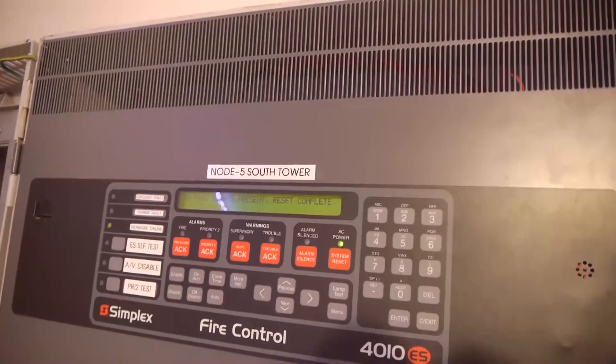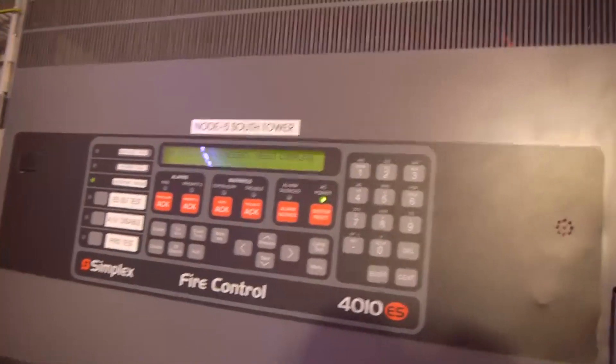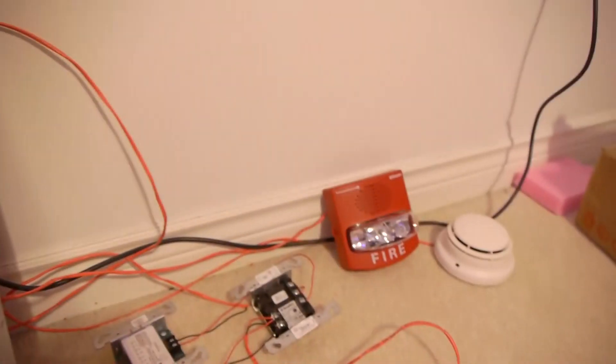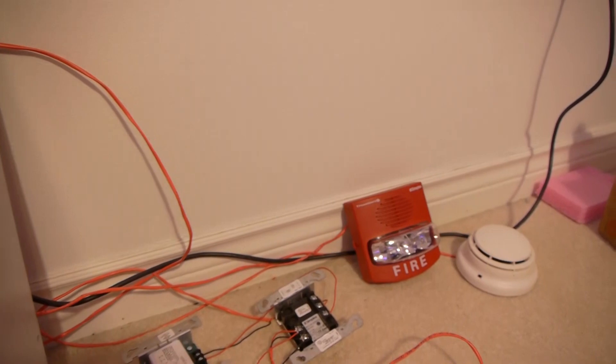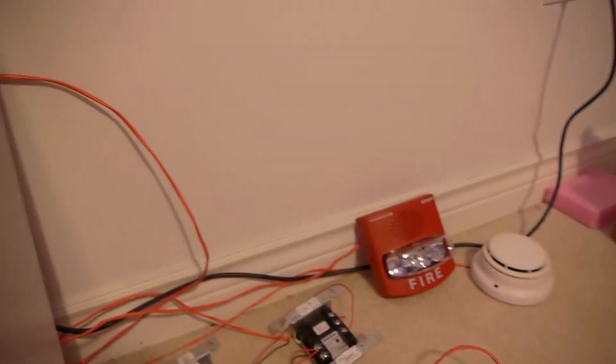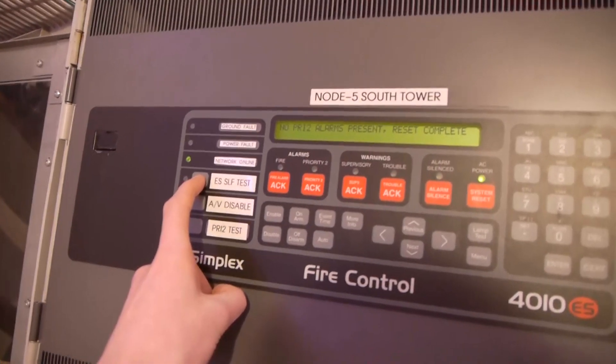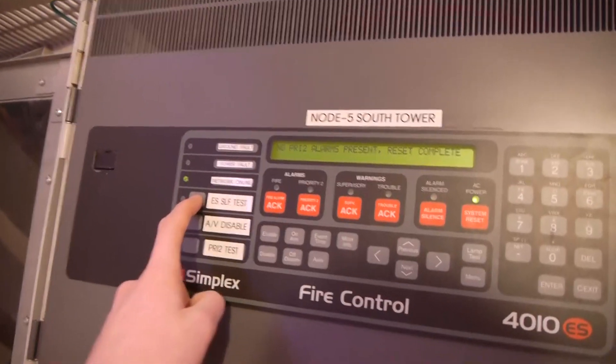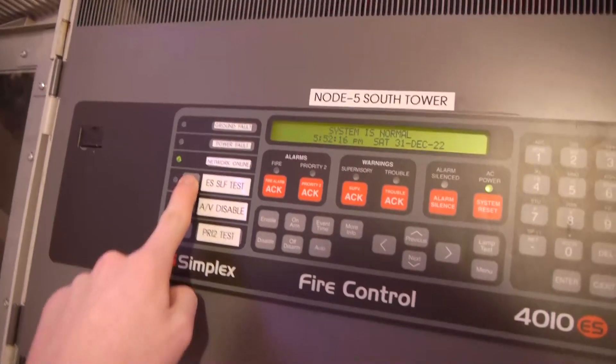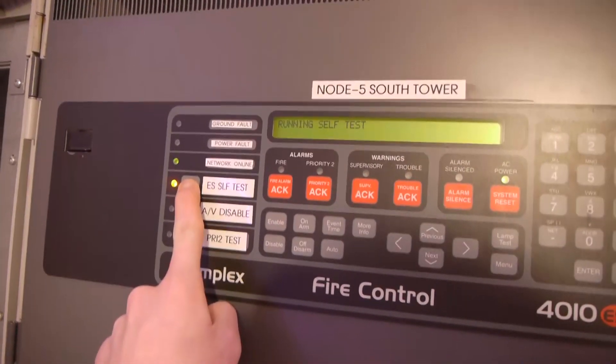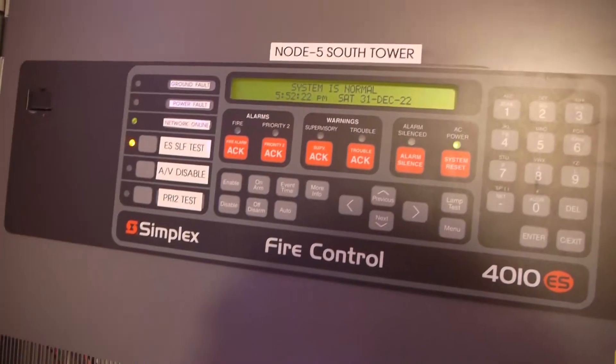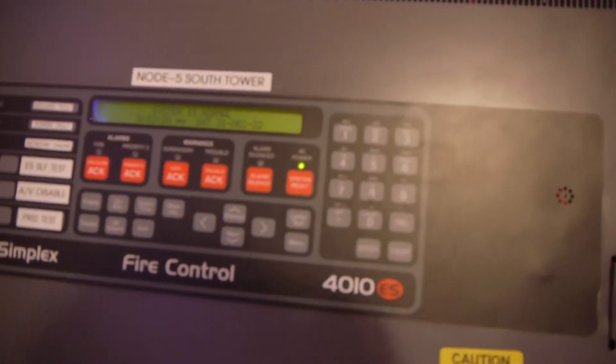So now we can go ahead, let's do it, ES self test. So basically, yes addressable devices, the panel can run a self test, and I'm not sure how the device knows if it's working or not, but it can tell if it actually makes noise and if it flashes, then it feeds that information back to the panel. So it's pretty cool technology. So now we can go ahead and hit self test. Now we programmed it to do a two second delay, so you have to hold it, because it does make the horn go off for a second. So we can go back to the system normal screen and hold it down for two seconds.